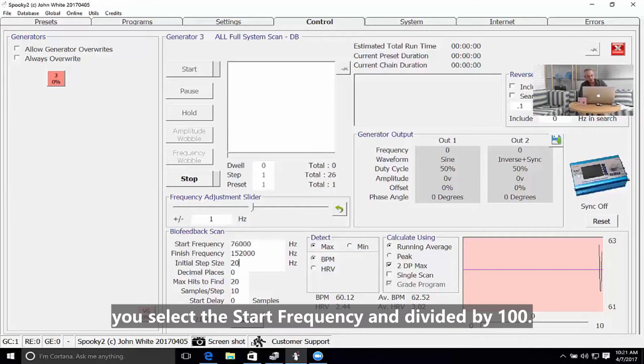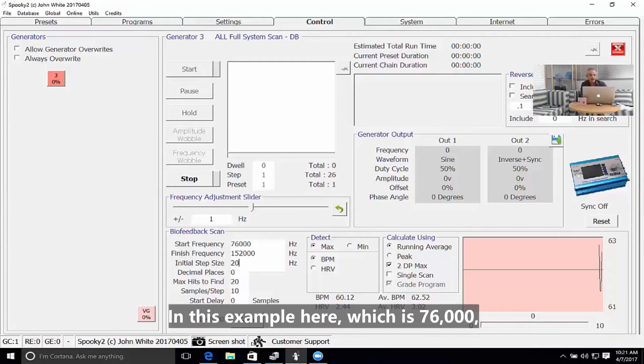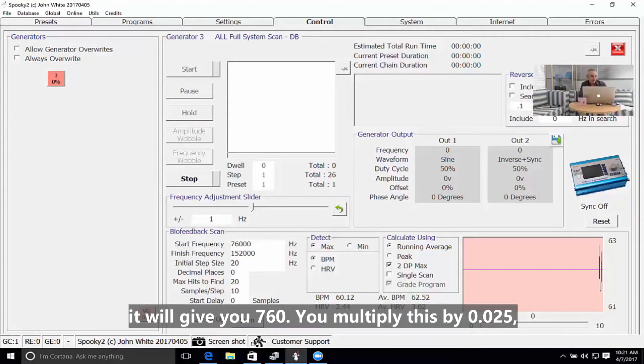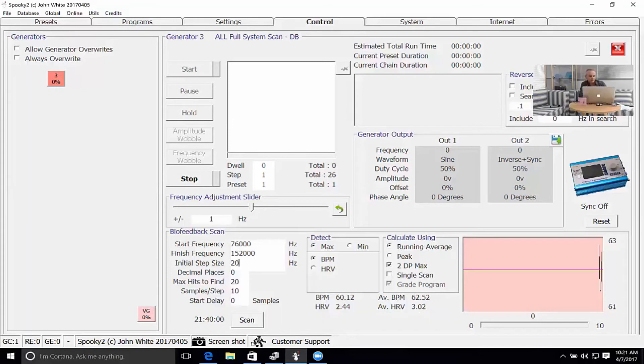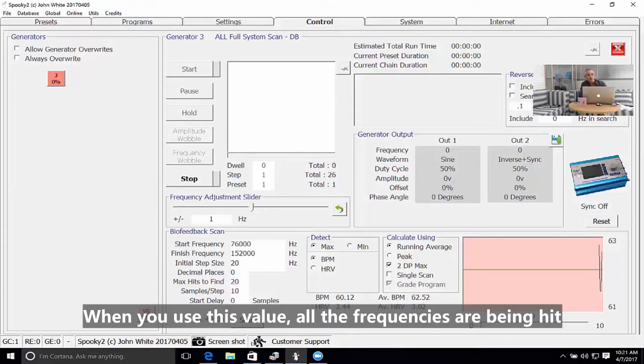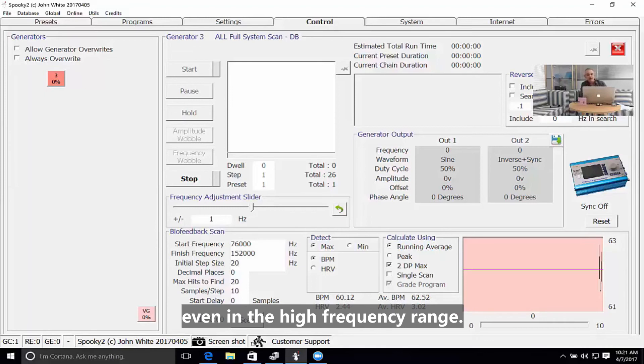You select the start frequency and divide it by 100. In this example, which is 76,000, that gives you 760. You then multiply this by 0.025 — that's 0.025% — and you get 19. We round this up to get 20. When you use this value, all the frequencies are being hit even in the higher frequency range.